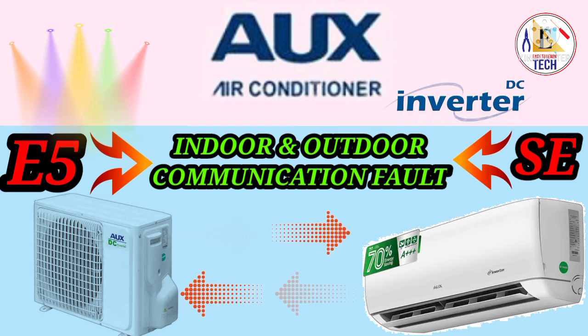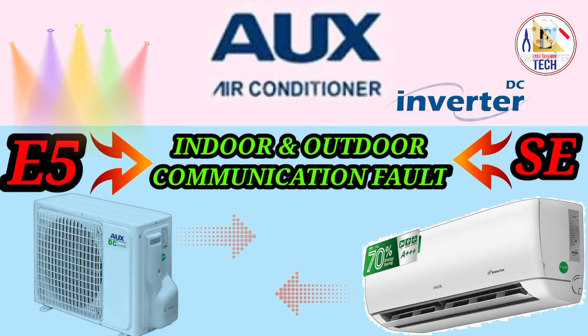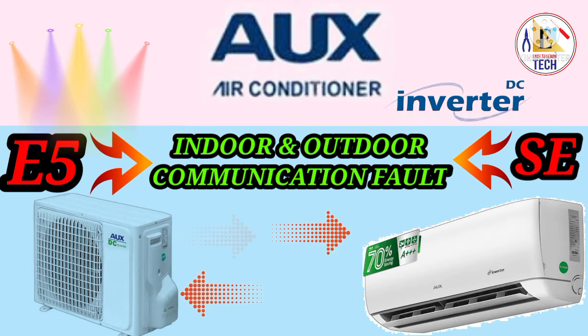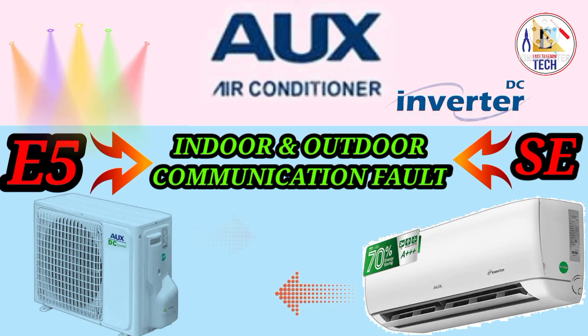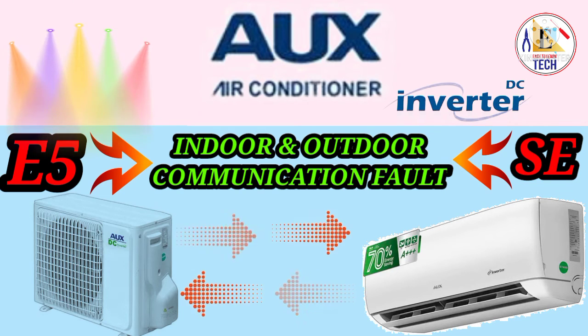At that time, first of all, you have to check the cable between indoor and outdoor to see if the cable is good or not. If the cable is good, then you have to check the terminals of your indoor as well as outdoor unit to see if the same wire is connected or not. If the same wire is not connected, connect it properly and start the unit and you will get the solution.